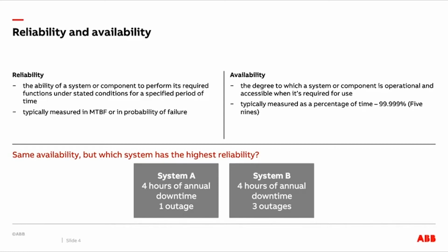Reliability of a critical power system can be calculated using IEEE P3006.8, the recommended practice for analyzing reliability data for equipment used in industrial and commercial power systems. This practice has not been widely adopted or accepted for data centers for several reasons.